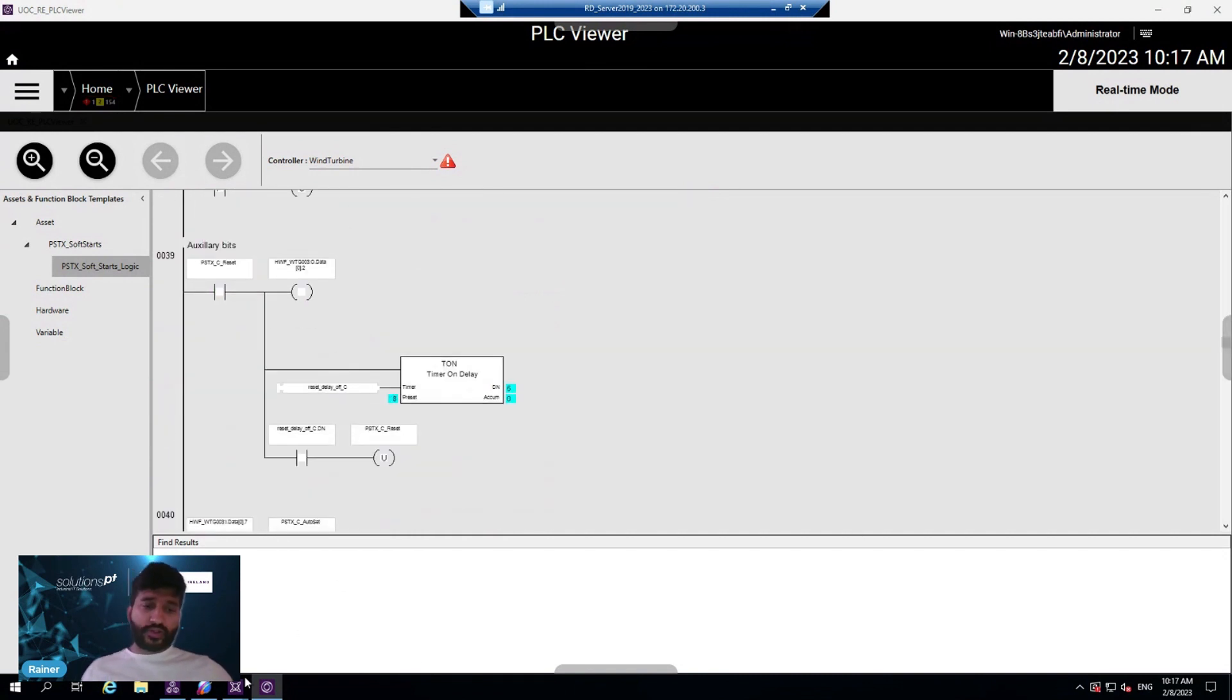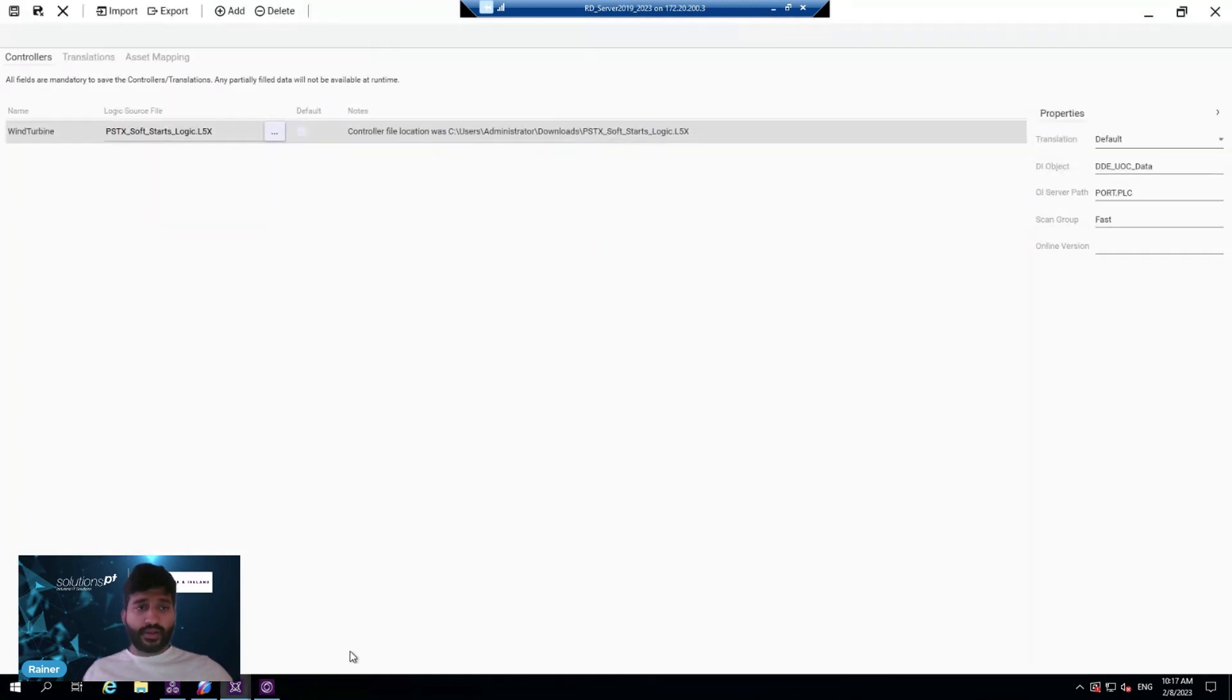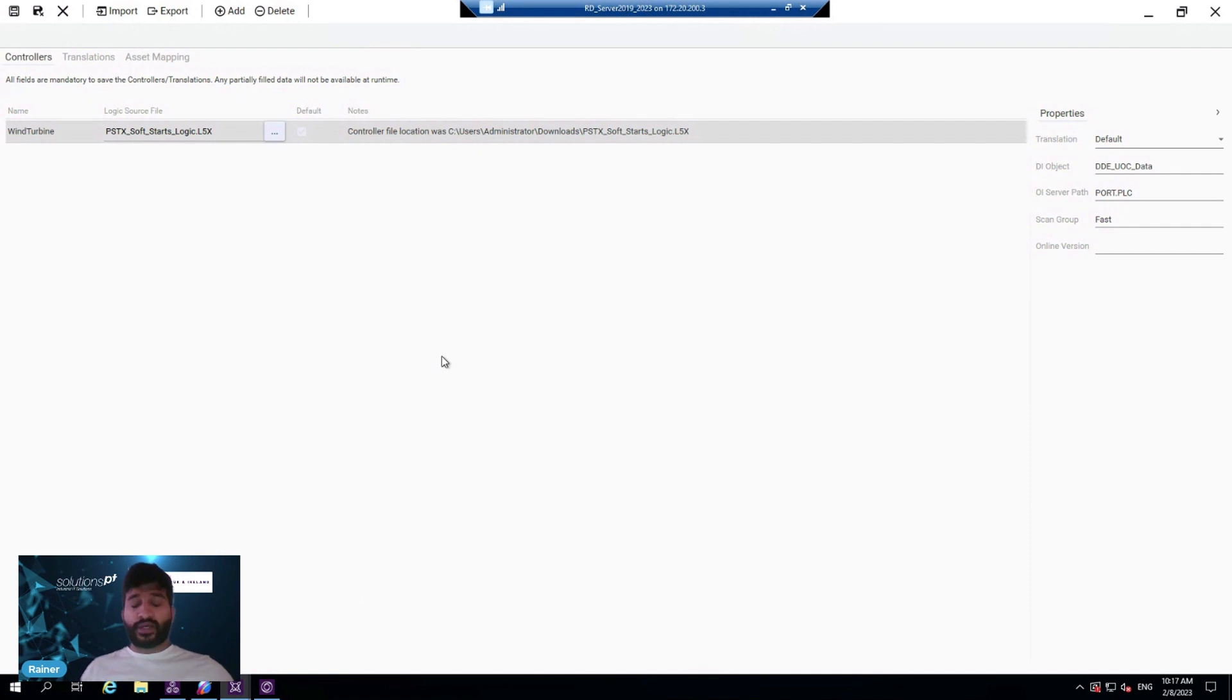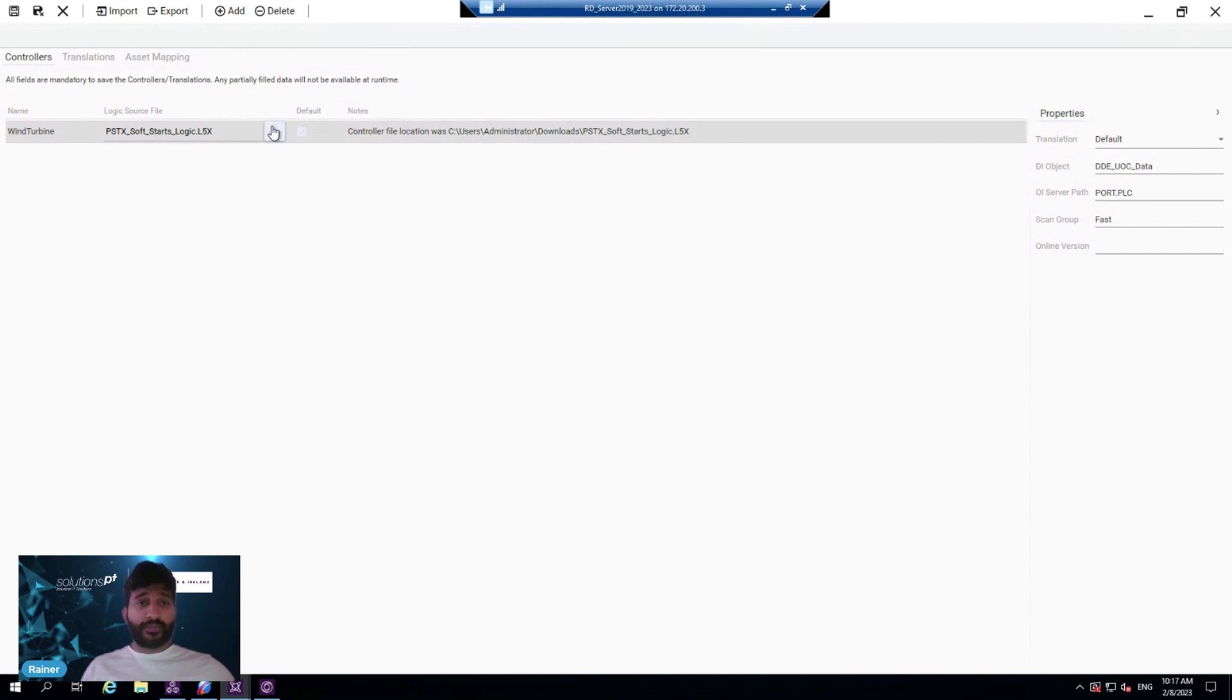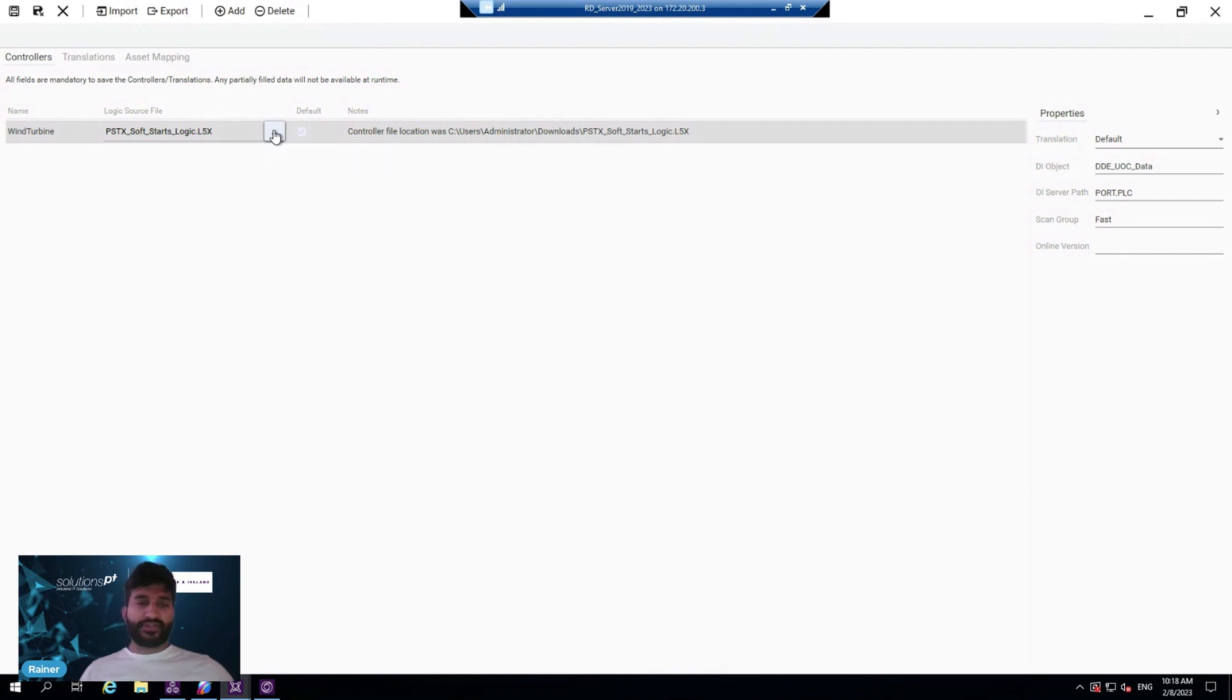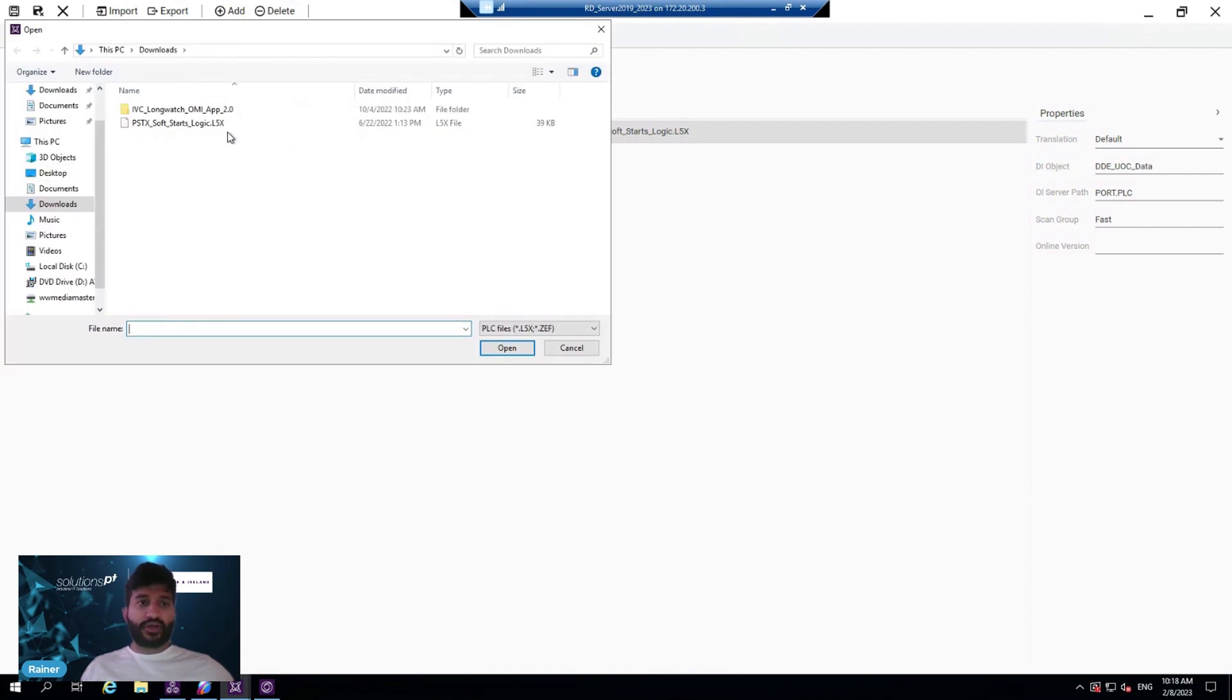Let's go to the backend to see how it works within the SCADA platform. We have an app called PLC Viewer, which is one of the OMI apps available within AVEVA OMI. It acts as a WPF wrapper that sits within the System Platform, pulls information and displays content to the operator or manager. From your PLC software, such as Studio 5000, you can export the rung and you'll get one of these formats. You can browse to the file and pull that in.